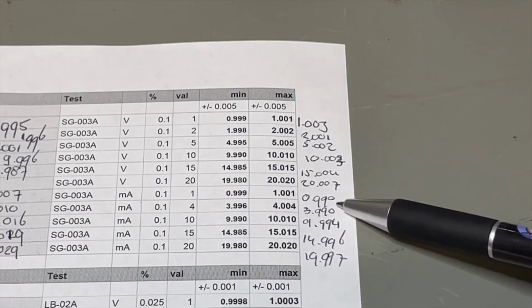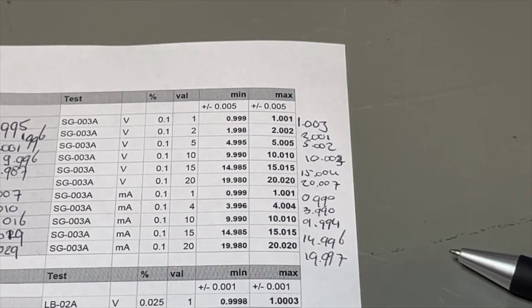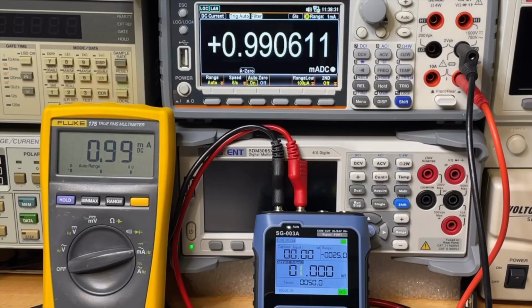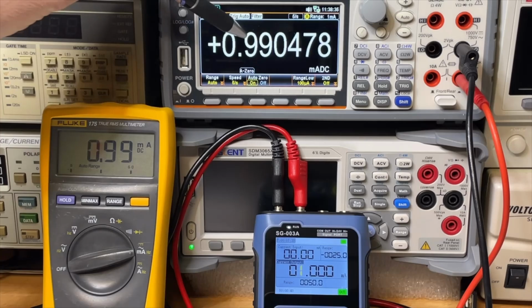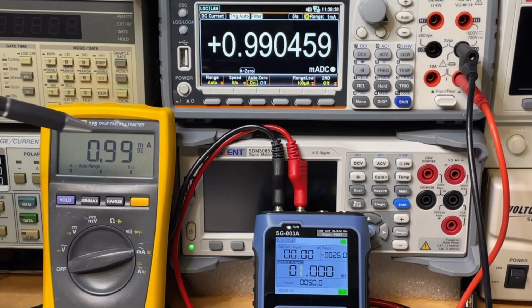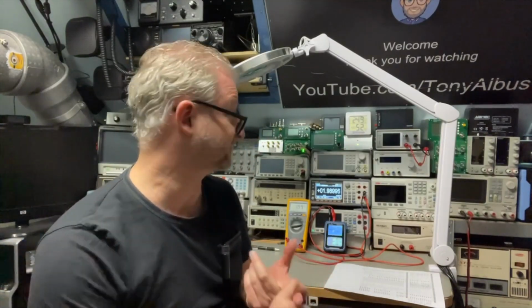So in the lower range it's a fraction too low, but again we probably don't see that on our 3.5 digit meter. Well, we actually can see it on this multimeter - here it's a bit low, and here it's a bit low, but this multimeter also has plus or minus 1 digit. So out of the box, the current was not spot on, while the voltage was, and it is even outside specs.